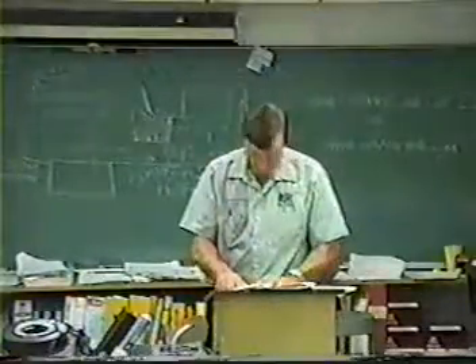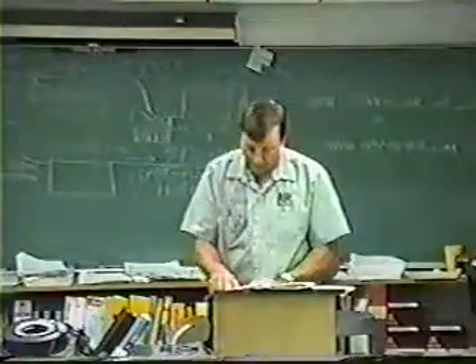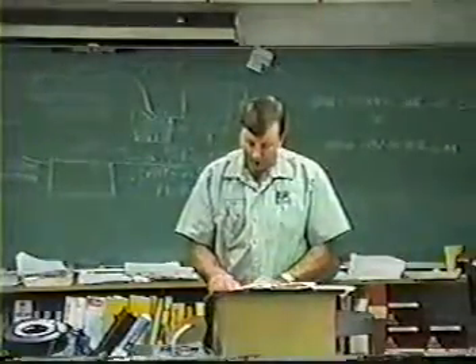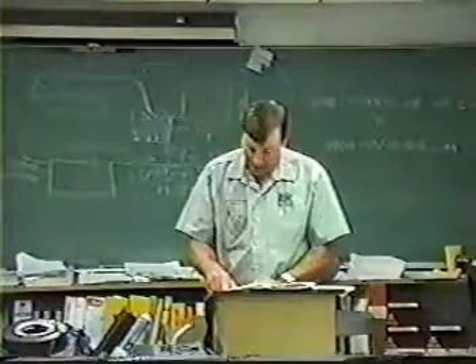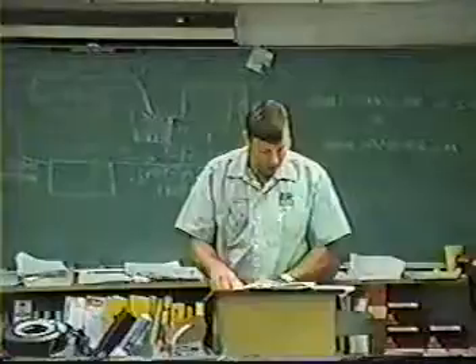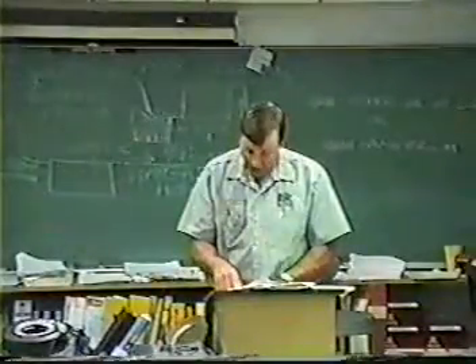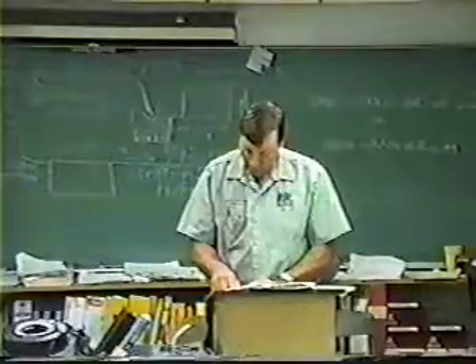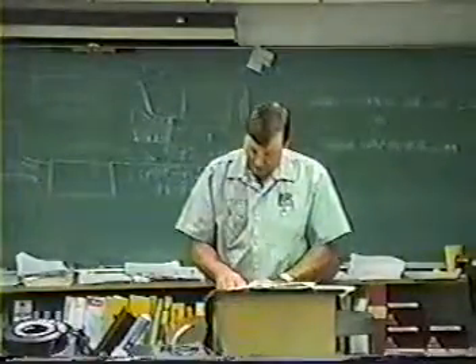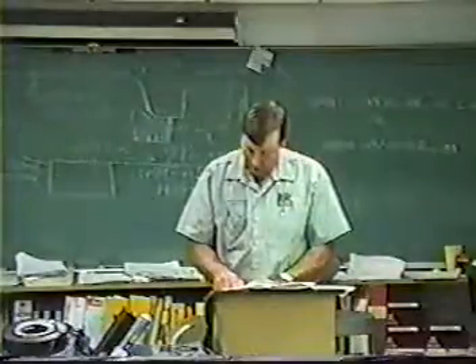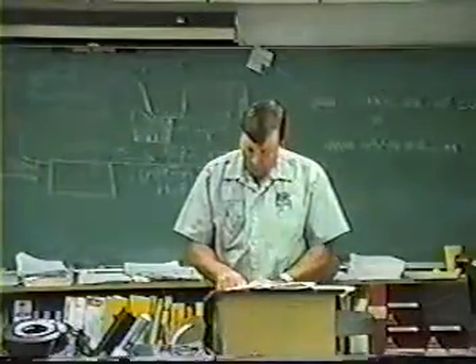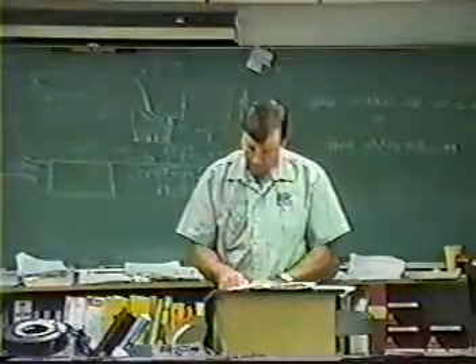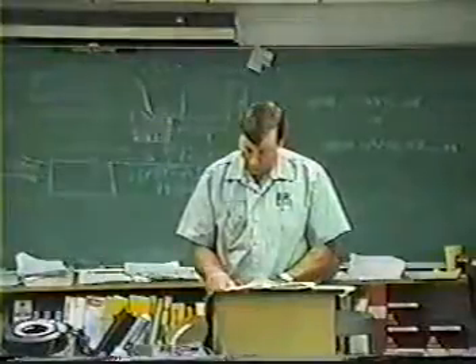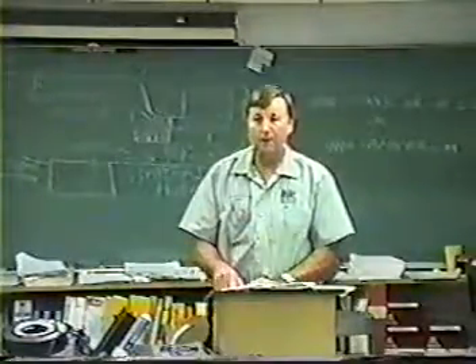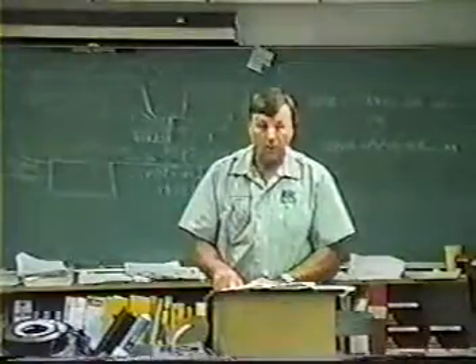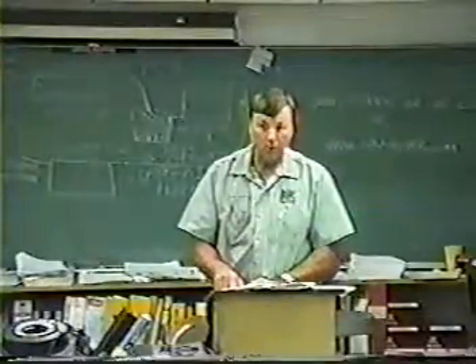Number 65. Exceptions to the required evacuation level for recovery equipment that require an appliance be evacuated to only 0 PSIG apply to appliances that: A, are being salvaged or filled with water or a substance that would damage the recovery equipment; B, have defective evaporator fan motors; C, have air-cooled condensers. Well, the answer to that one is A, filled with water or a substance that would damage the recovery equipment. You guys understand that one now? If it's got water in it, it's going to damage the equipment. So all you've got to do is go to 0 on that.